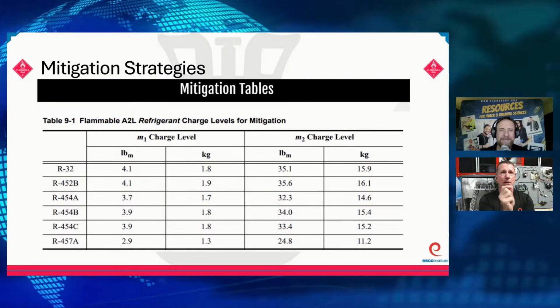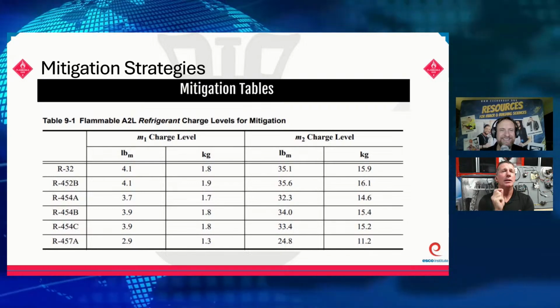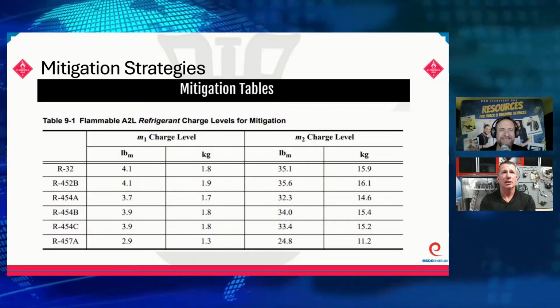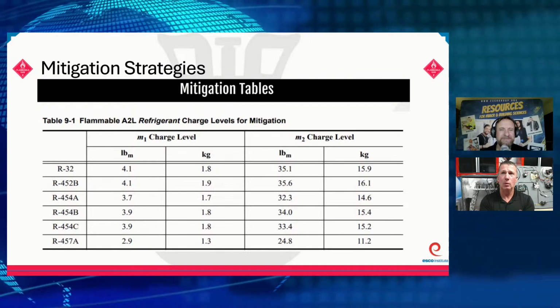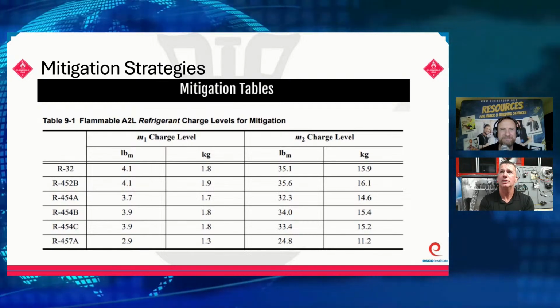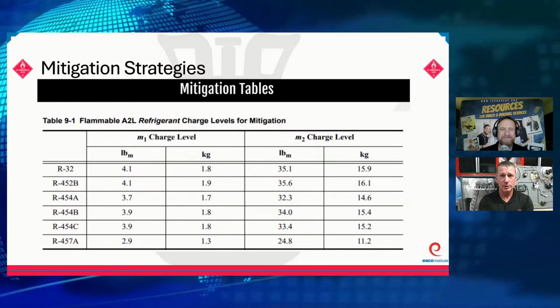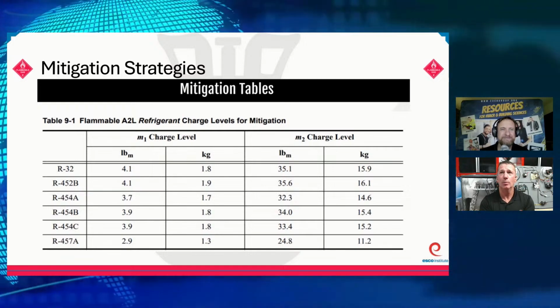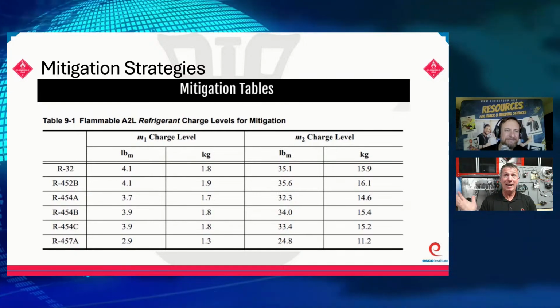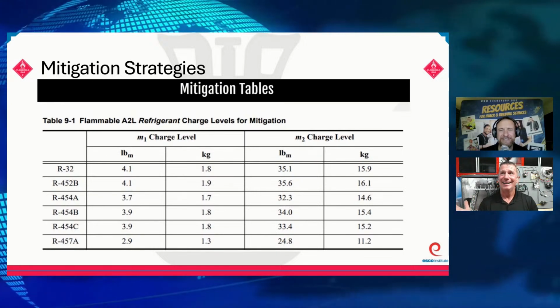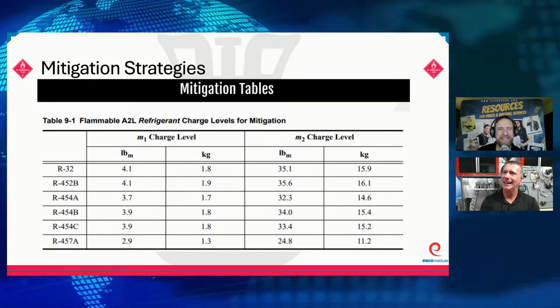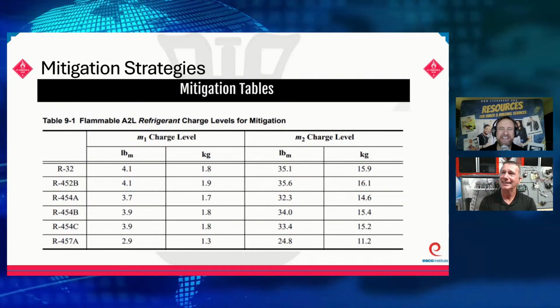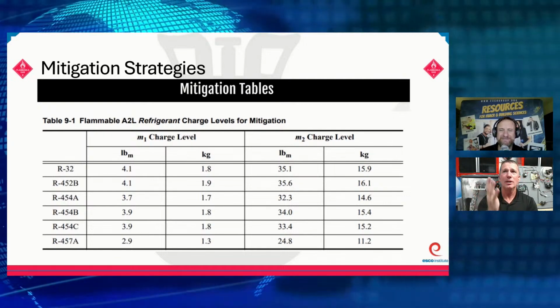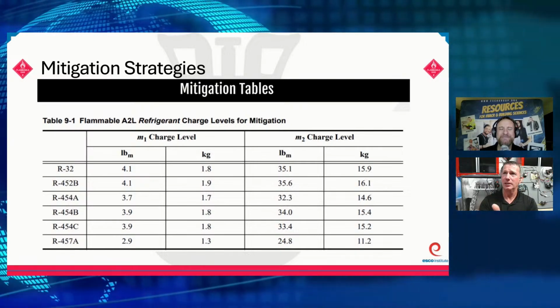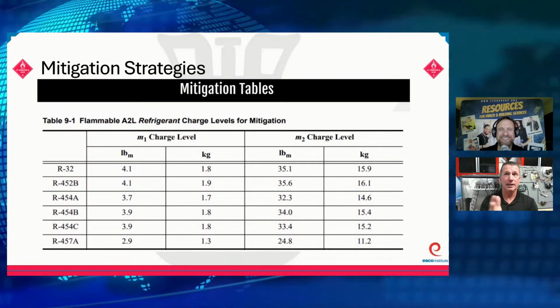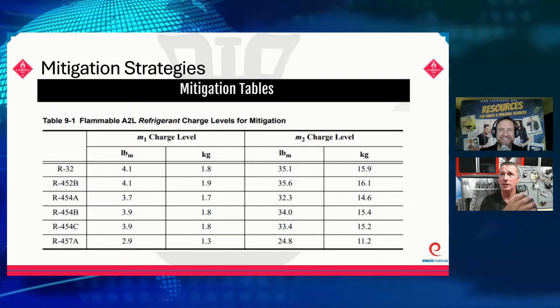Okay, so if we can fall under that M1 charge level, so 4.1 pounds of mass of R32 within a system, or 3.9 pounds of R454B, we don't even have to have mitigation, Ty. That's right. My mini split doesn't have any mitigation whatsoever because it falls under that threshold. Okay, so you ordered an R32 ductless mini split, correct? Yes, that's correct.